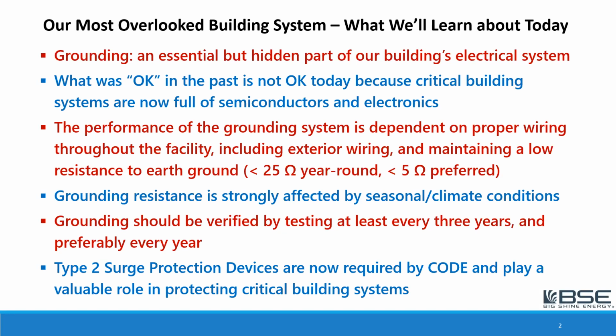And maintaining a low resistance to earth ground is very essential. We'd like to see that always be at least below 25 ohms and preferably below 5 ohms. There's no fixed perfect number, but the lower the better. The grounding resistance is strongly affected by seasonal and climatic conditions. Grounding should be verified by testing at least every 3 years, and preferably every year.